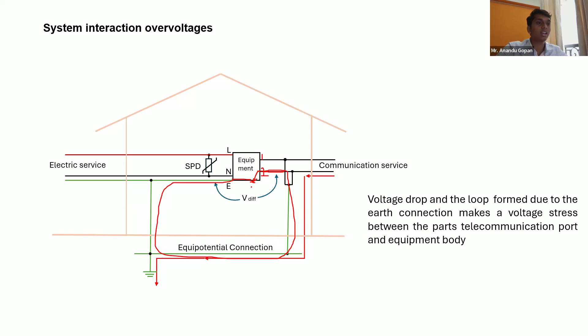Due to the voltage drop, a loop will be formed, and there can be a spark over - the insulation will be stressed at that point. So you have a mesh bonded network. Till now, I'm telling you, if you have your mesh bonding system, you don't need to consider this. What is this mesh bonding system?